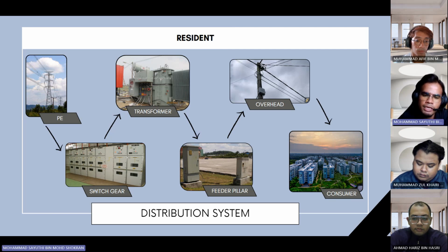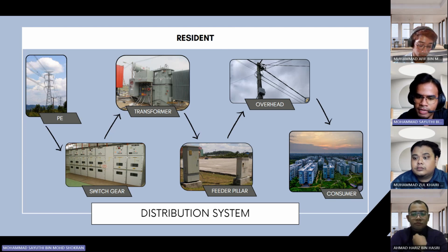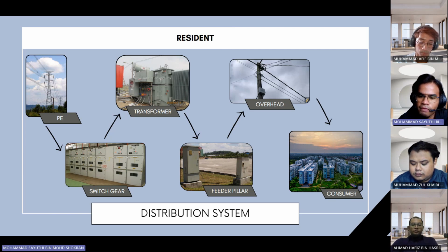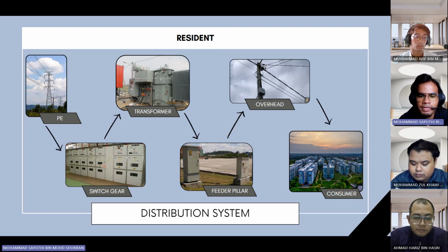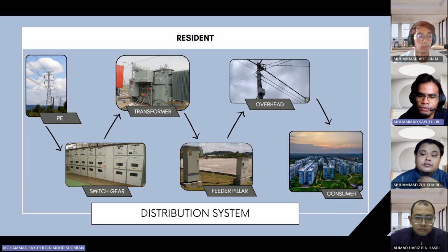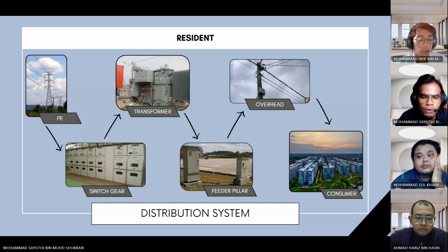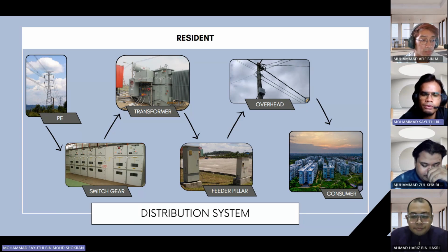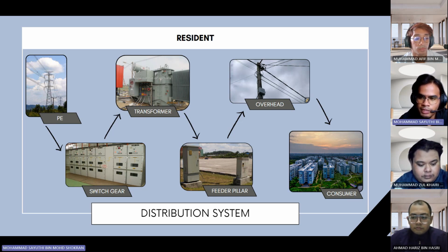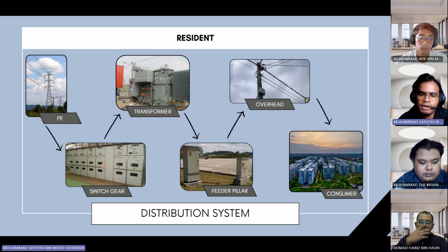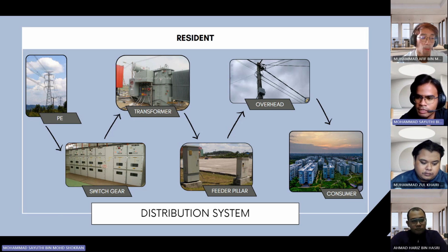The RMU may use different arc interruption media, such as air, SF6 (sulfur hexafluoride) gas, or vacuum, depending on the specific design and application. SF6 gas is commonly used in RMUs for its excellent insulating and arc quenching properties. The RMUs are equipped with a load break switch, which allows for the interruption of current flow under normal operating conditions. This feature is useful for isolating a section of the distribution network for maintenance or repair purposes without disrupting the entire system.